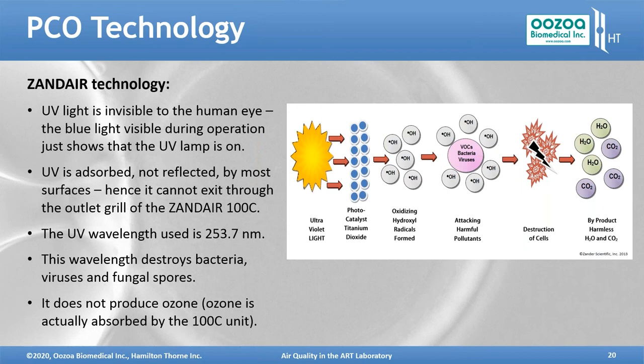At this wavelength, you do not produce ozone. In fact, this sort of technology actually adsorbs any ozone that might be in the area, so it's very good. So ultraviolet light in conjunction with the titanium dioxide produces oxidizing hydroxyl radicals, and these will attack the VOCs, the bacteria, and the viruses. It'll destroy cells, inactivate viruses, and breaks down the VOCs, as I said, ultimately to CO2 and water vapor.